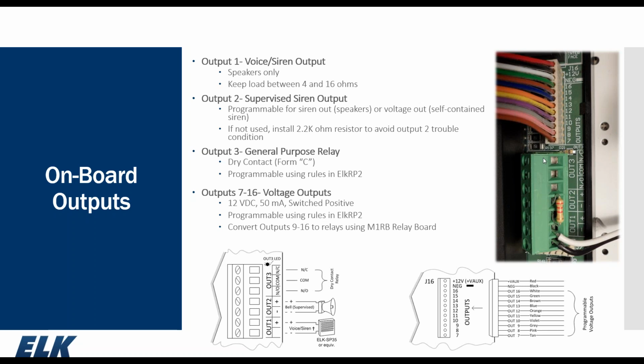These are our low voltage outputs 7 through 16. Each one of these is positive switched 12 volt at 50 milliamps each. They're certainly capable of driving low current relays, piezo sounders, LEDs, things of that nature. We offer the M1RB relay board, which connects to J16, and that will convert outputs 9 through 16 into actual Form C relays. You still have 2 low voltage outputs, 7 and 8, but with the M1RB, we now have physical dry contact relays, 9 through 16. These relays are capable of switching up to 120 volt at approximately 8 amps. So they're beefier relays for controlling higher current loads.